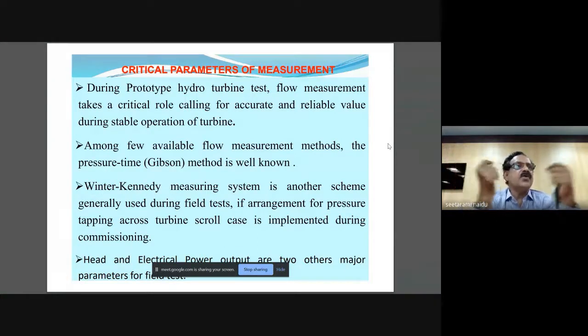Recently we have conducted it there. You must have seen a venturi meter or nozzle meter. The difference of pressure between one tapping and another tapping is the measure of discharge. In the same way, in a scroll casing, two high-pressure and low-pressure tappings are selected. That pressure is monitored, and that gives the discharge. But for a running plant it can't be done, because it has to be connected to the scroll. So it has to be done during commissioning.